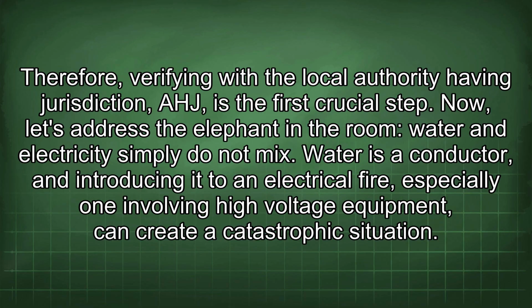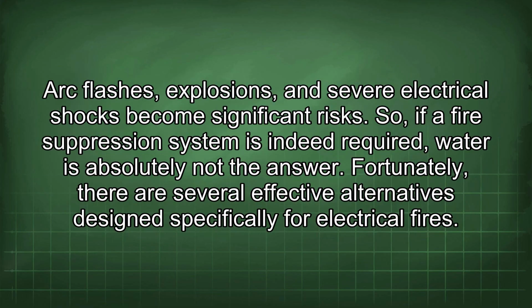Now, let's address the elephant in the room. Water and electricity simply do not mix. Water is a conductor, and introducing it to an electrical fire, especially one involving high voltage equipment, can create a catastrophic situation. Arc flashes, explosions, and severe electrical shocks become significant risks. So, if a fire suppression system is indeed required, water is absolutely not the answer. Fortunately, there are several effective alternatives designed specifically for electrical fires.